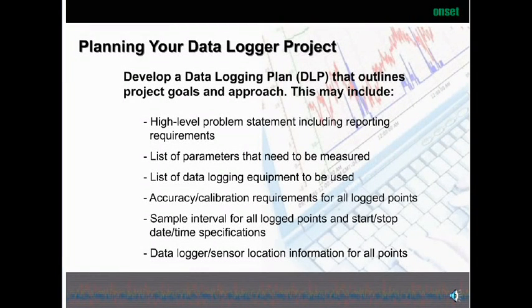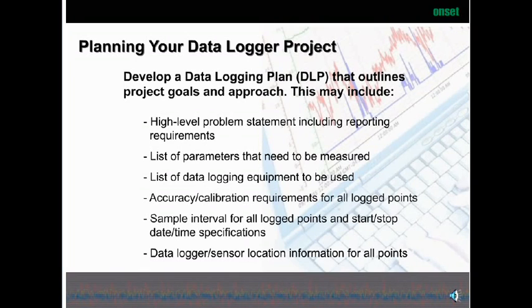Accuracy can use up memory. It can define which type of piece of equipment you need, how accurate the temperature or pressure — those types of things. Sample interval for all log points and start, stop, date, time specifications. It's very important to understand that prior to deployment, because if you take the sampling rate too high, sometimes it will load up the data logger memory. So you want to make sure you have enough memory in your data logger for the time period that you're trying to sample.